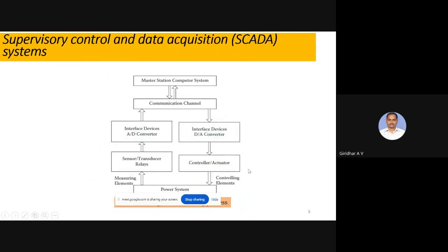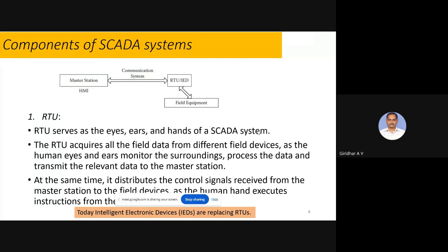So these are typical measurement elements and sensors, how they convert into digital data and pass into communication channels, again connected to the master station. This is the overall picture. If you look at the components of SCADA systems, there are field devices like CTs, PTs, switches data, RCBs data, everything related to field data, and it will be passed to RTUs. Nowadays IEDs, intelligent electronic devices, are also used for multifunctional monitoring, control, and protection.